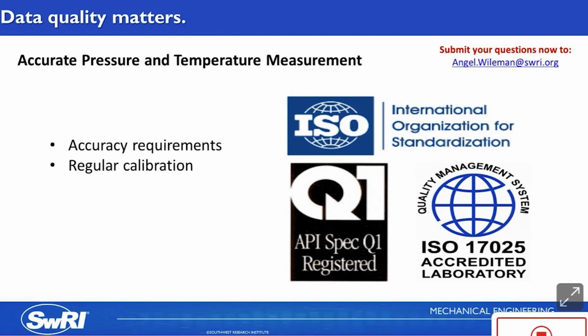And part of our internal quality system is keeping an instrument calibration database, and it has records of all of our instrument calibrations. The accuracy of the instrument should be determined based on the measured accuracy during calibration, not the accuracy that's stated by the instrument manufacturer, because this is typically exaggerated, and we see very large differences between the stated accuracy and the actual accuracy, even with brand new instruments.